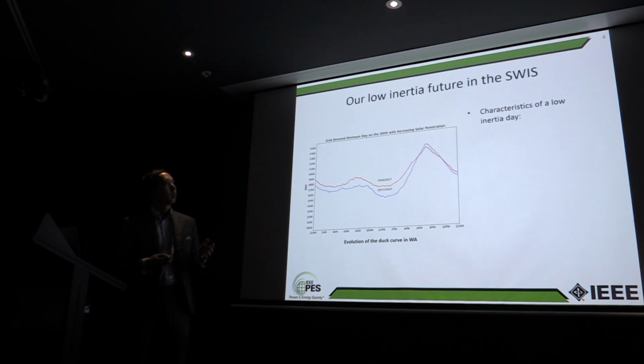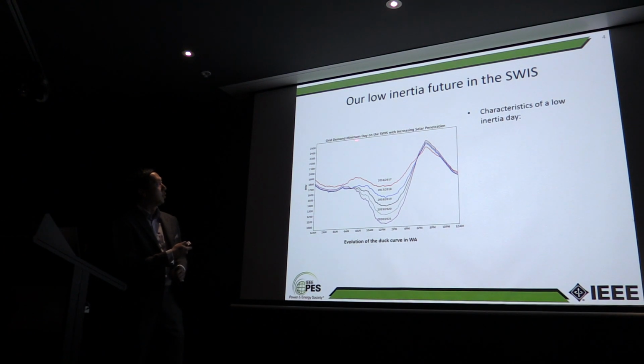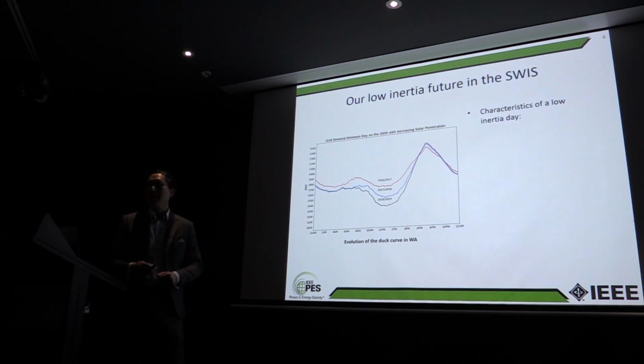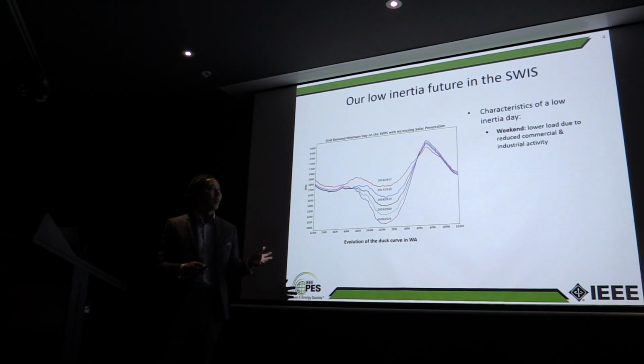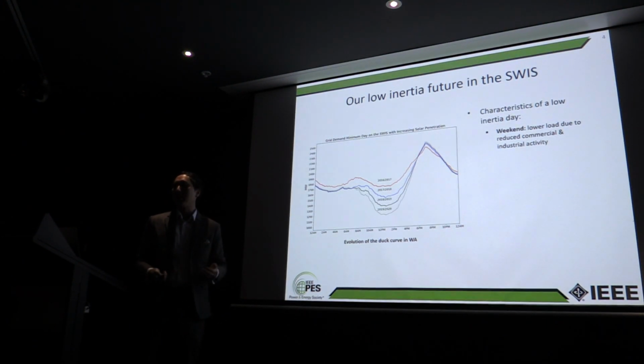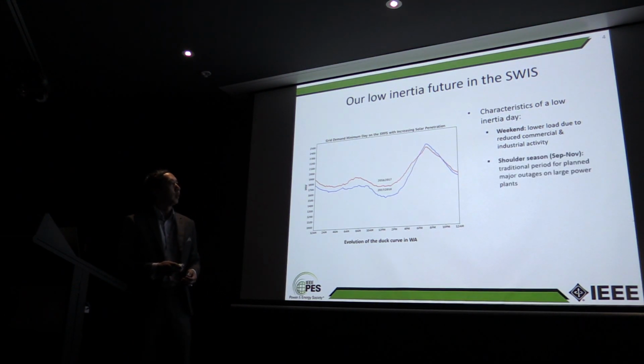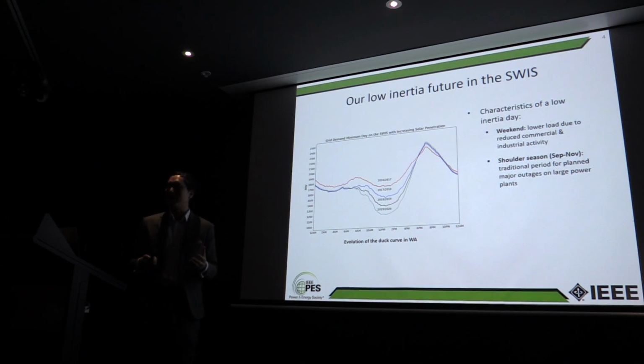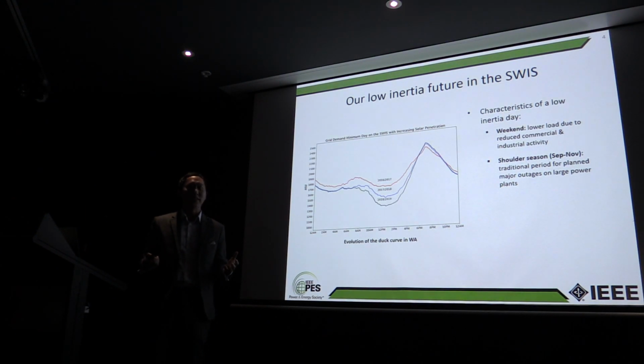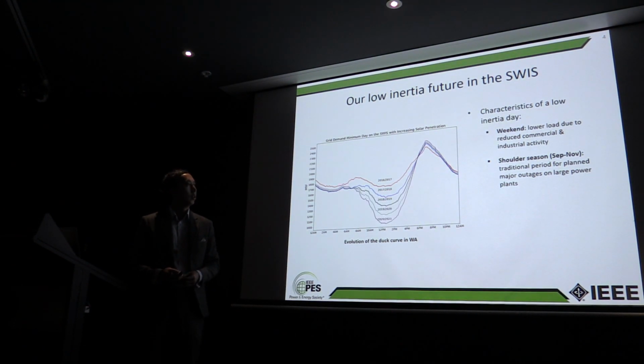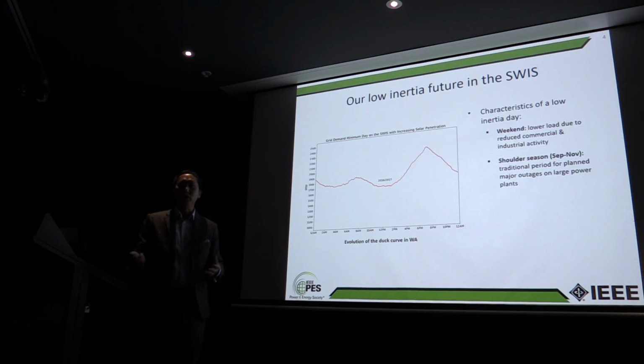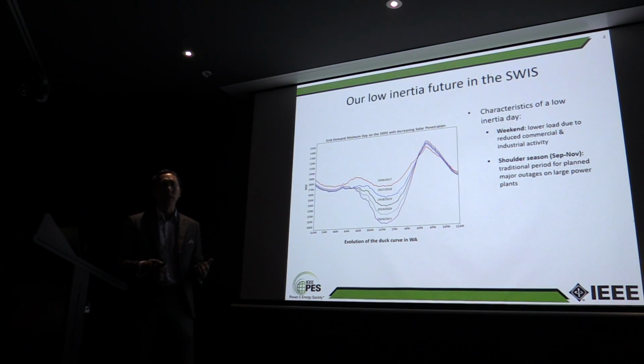And so the characteristics of a really low inertia day. This, by the way, is the minimum day of that particular year in the SWIS. Anyway, the characteristic for a low inertia day is usually that it's a weekend. So you have lower load during the weekend, with less commercial and industrial activity. Second, it's usually in the shoulder season. The interesting point here is that this is the period where we usually have the major outages for maintenance of the large plants in the system. So the big coal units of Muja and Collie, the large combined cycle units at NewGen, Kwinana and Cockburn. And they have large inertia. You take them out of the system because they're on maintenance, and we reduce the total amount of system inertia.